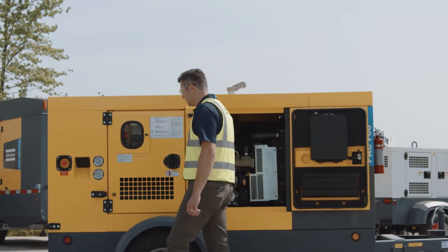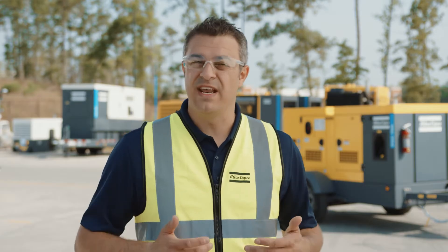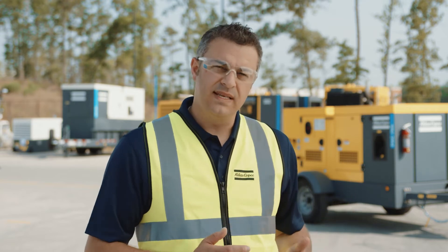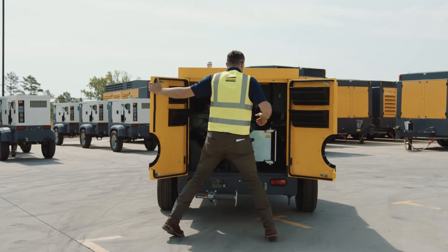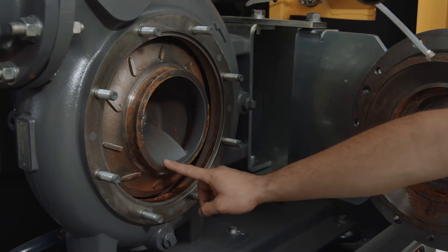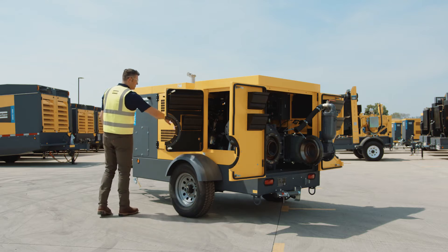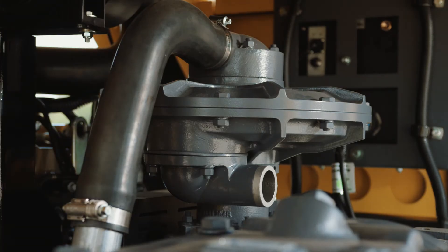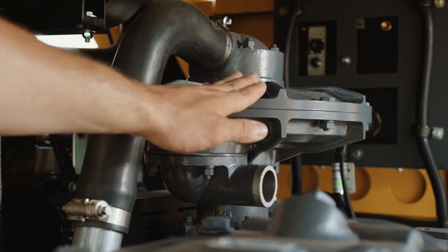When it comes to performance, what's important to you is to get the job done quicker with the least amount of energy invested. Our PAC-F66 and F88 uses a closed impeller type with up to a maximum of 12 inches in diameter and still passes a 3 inch spherical solid. We have created a design that gives you up to 82 percent pump efficiency to get the job done quicker. The priming system is powered by a diaphragm vacuum pump that delivers 50 cubic feet per minute. The higher the performance, the faster our prime and the quicker we start pumping.